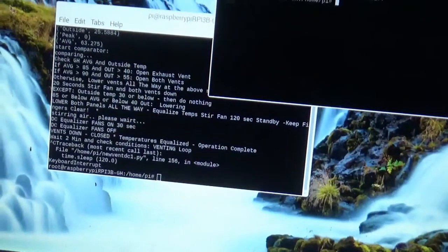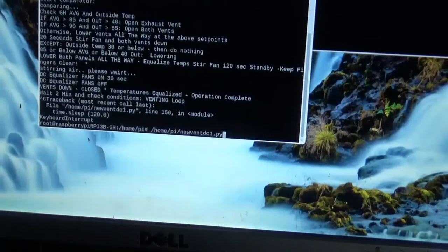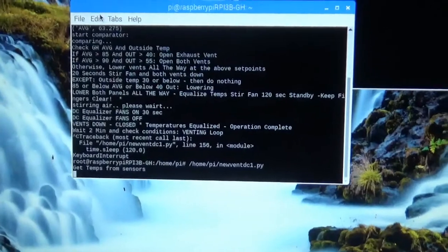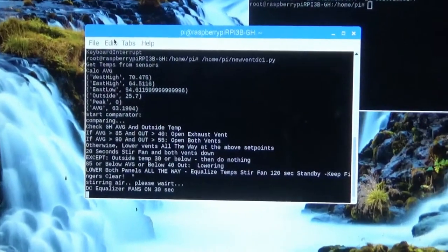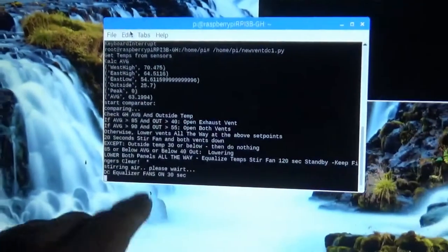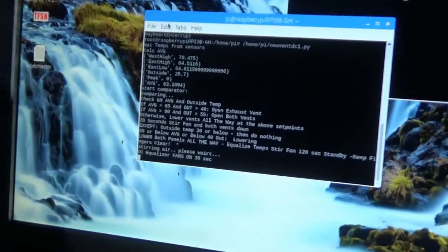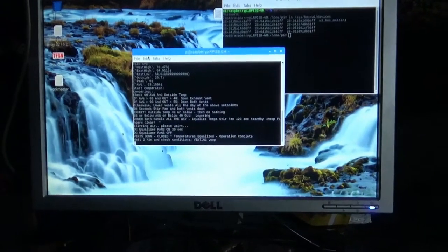When I do the list you can see four times three — 12 sensors show up. East high, west high, east low, west low — four ground temperature sensors, that's eight — a water temperature sensor and a couple others. They show up like they should immediately. I have the script open and I'm starting it up — you can see it's grabbing temperatures like it's supposed to. The DC equalizer fan part of the script comes on for a 30-second burst of fan one and fan two. You can see the red light on the relay board indicating those are on.